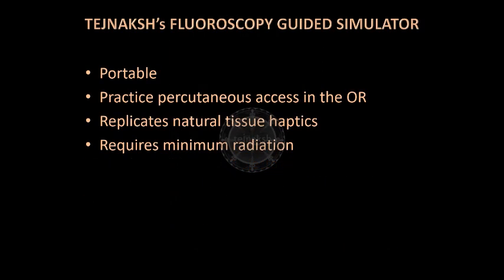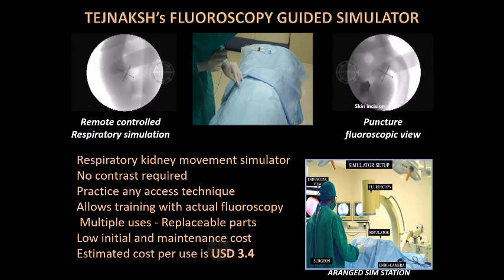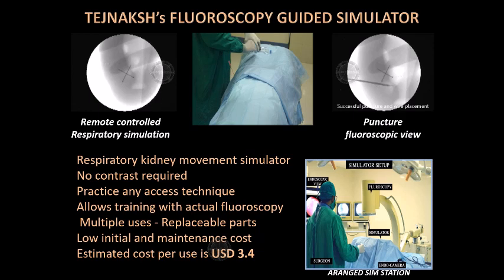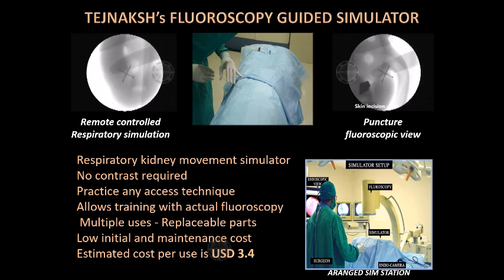Tejnaksh's fluoroscopy-guided simulator is a portable and lightweight simulator used to practice renal access in the operating room using the fluoroscopy machine. The simulator requires a minimal radiation setting and replicates natural tissue haptics. Once assembled onto the table, the simulator mimics an actual patient. It is provided with a remote control which allows the mentor to turn on and off the renal respiratory movement simulator. The trainee can ask the assistant to stop the respiration in any phase for puncture. It does not need contrast installation. On successful puncture, saline can be aspirated from the PCS and guide wires placed into the kidney and ureter. The simulator uses replaceable components, hence has a low initial and maintenance cost.